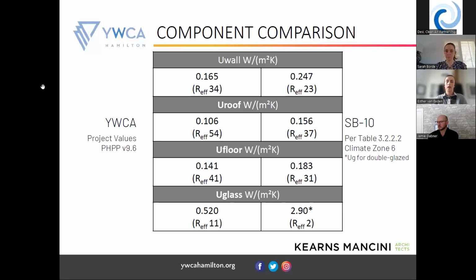When we break it down like this, you can see the massive difference between the R values in the assemblies. If we isolate the space heating demand for a building, the Y's space heating demand was around 12 kilowatt hours per square meter per year. If we had followed the SB10 values, it would have been 3 times as much, around 37 or 38 kilowatt hours per square meter per year. So it really makes a big difference, these independent values.